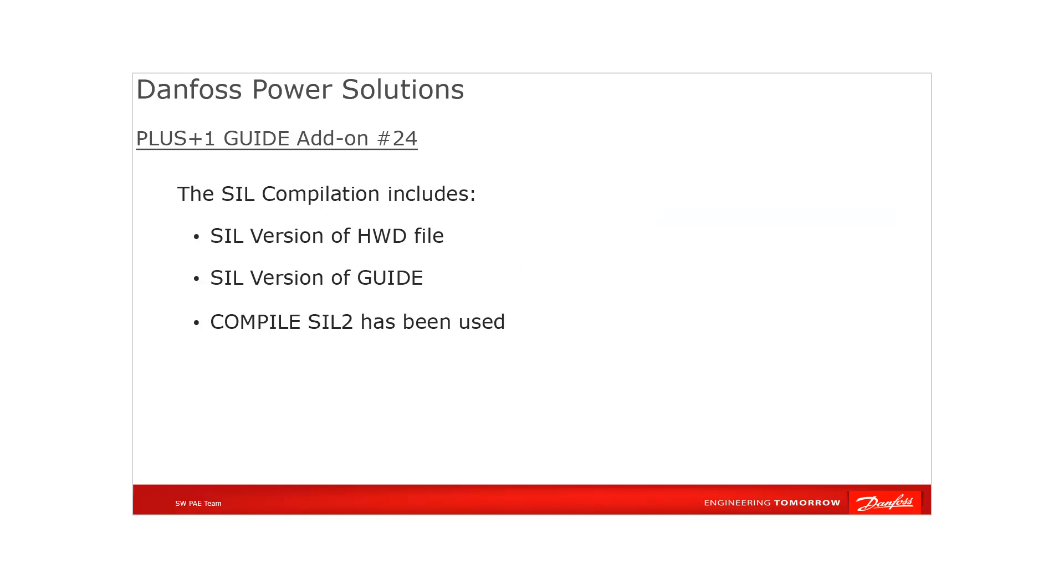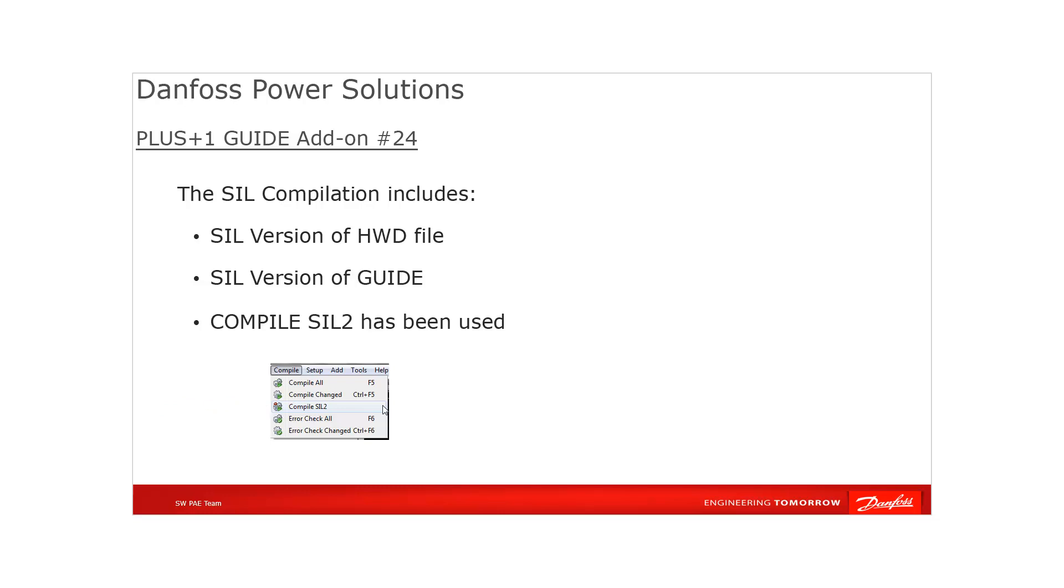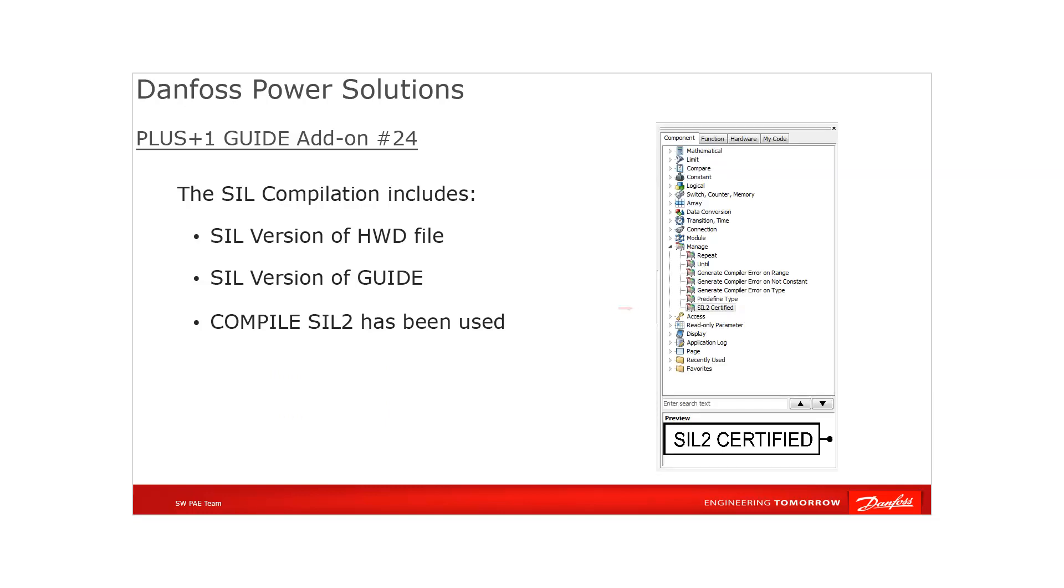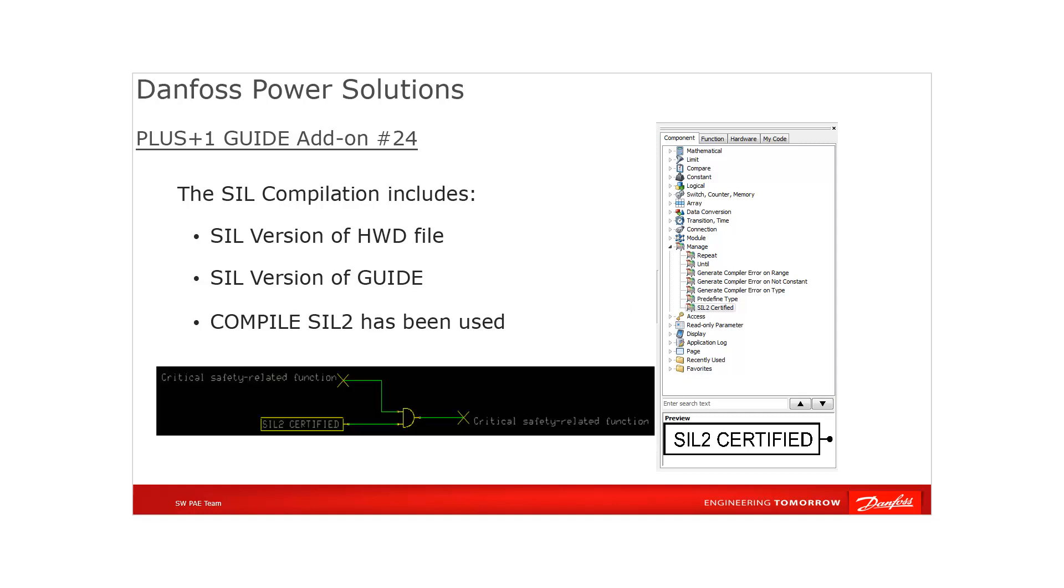If all these mentioned conditions are fulfilled, the Compile SIL2 button will be visible in the menu bar and compile of the safety-classified application possible. In addition to that, a SIL2 certified component will be available which can be used in SIL2 applications to indicate the fulfillment of requirements for a SIL2 certified application. This component provides a true signal on the output if the SIL2 compile process has been done correctly. That output can then be used to manage or control some critical safety-related functions inside the safety application.